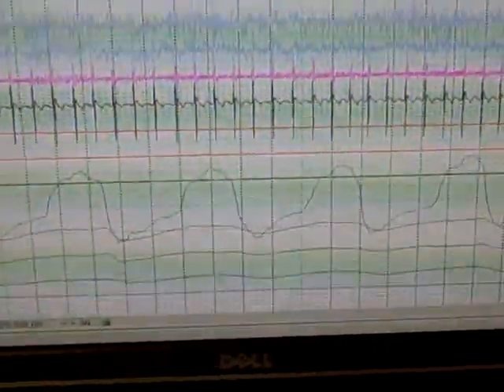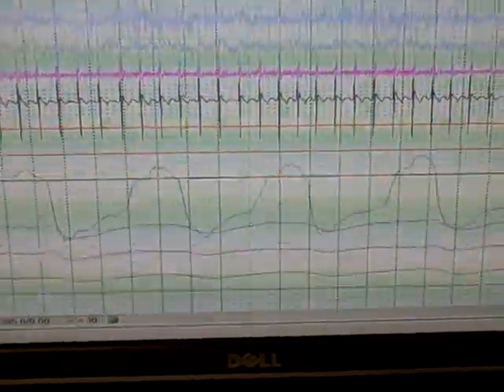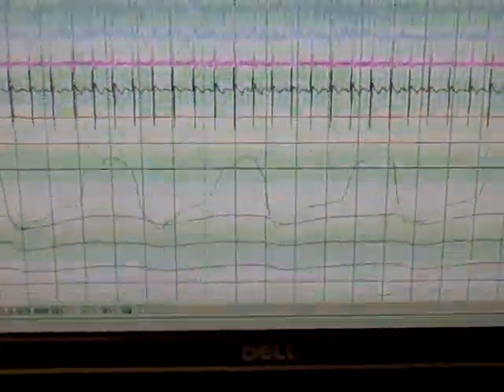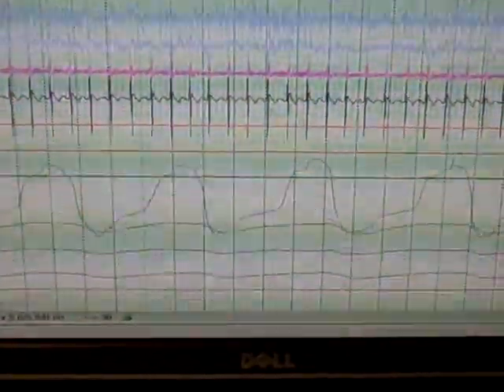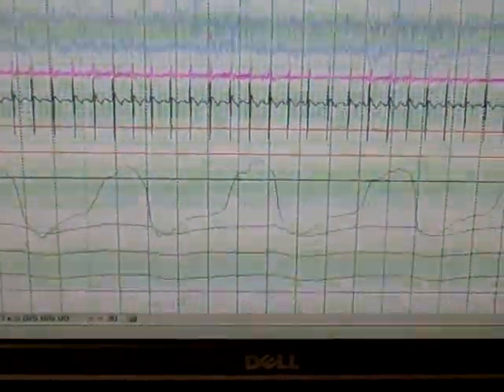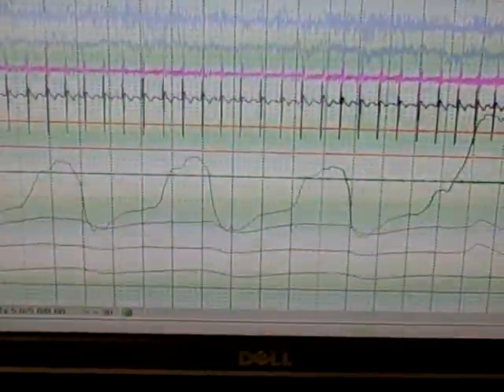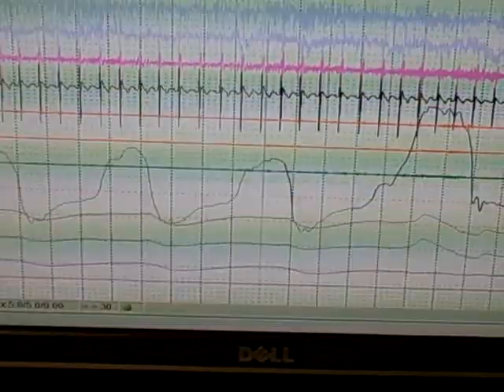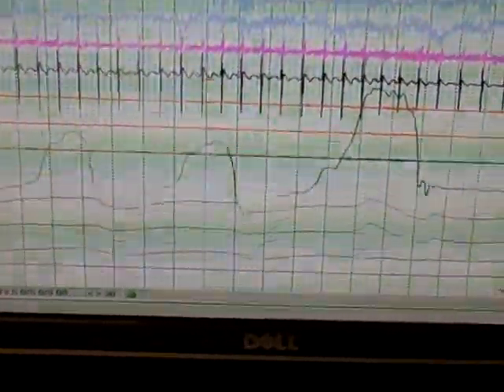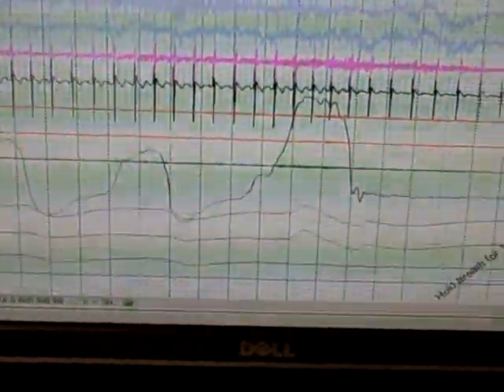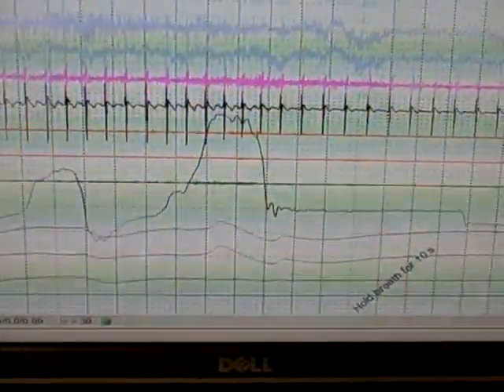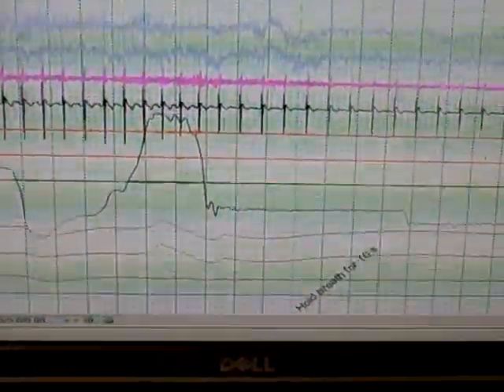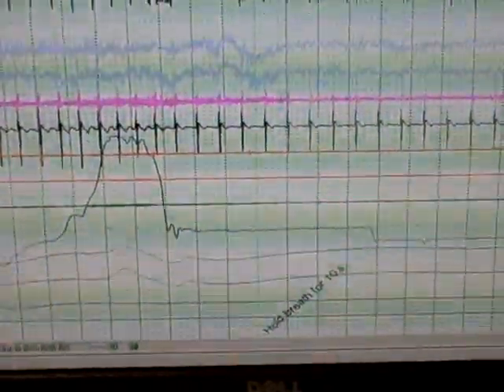When you're ready, I need you to take a deep breath in and hold it for about 10 seconds or as long as you can. And again, if you keep it to the bottom of the screen, you'll notice that the flow ceases and all belts remain flat. That's showing that the patient is not breathing. It's coming into the screen bottom right now. Excellent. Go ahead and start breathing, and you'll see the waveforms start to come back.